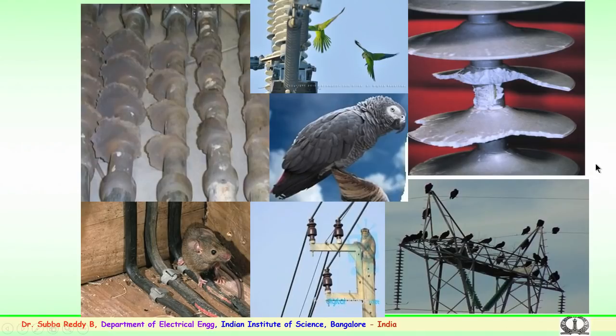There are again failures due to several of these aspects, because of the birds or because of the animals, which have to be properly considered or taken care of during transportation or storage. So, here, as you see, many of the insulator surfaces are being chipped off either by birds or by rodents. This would cause the entire creepage to come down and cause flashover, or you cannot use the insulators for the stringing.